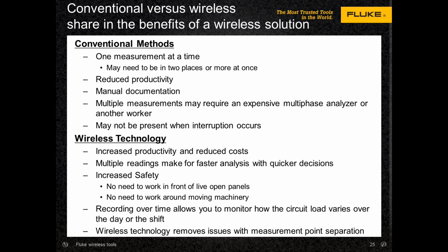This is just a summary of conventional versus wireless. Conventional methods are one measurement at a time, and you may need to be in two places at once, which reduces your productivity and increases your cost because you have to have a helper. You may need to write the readings down and build those into a report. Multiple measurements on a 3-phase system may require a 3-phase analyzer, which is expensive and not as prevalent as individual tools. And you may not be there when whatever it is happening happens.